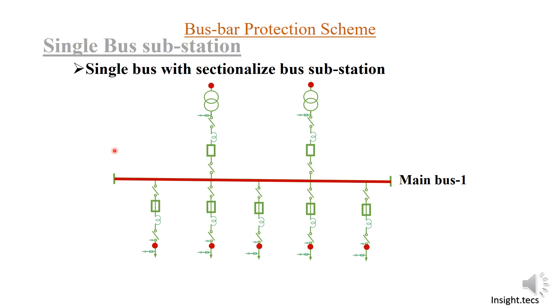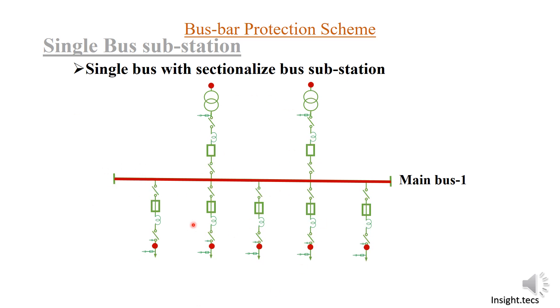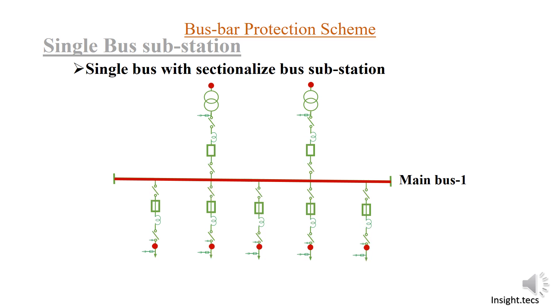There are a few drawbacks of this single bus arrangement scheme. If you want to do maintenance of the bus conductors, any of the jumpers or conductors connected through this main bus, you will have to take the outage of the entire substation — you have to shut down both transformers and isolate the main bus. So the only drawback is that for maintenance you have to take the shutdown of the entire substation.